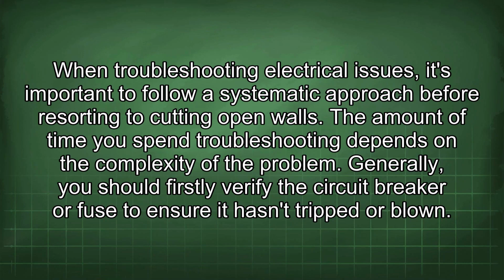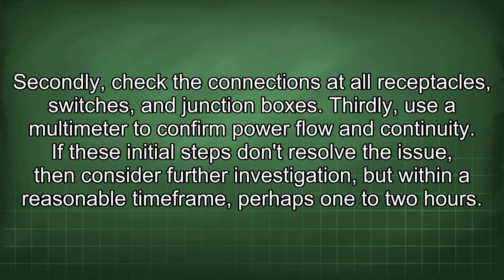When troubleshooting electrical issues, it's important to follow a systematic approach before resorting to cutting open walls. The amount of time you spend troubleshooting depends on the complexity of the problem. Generally, you should firstly verify the circuit breaker or fuse to ensure it hasn't tripped or blown. Secondly, check the connections at all receptacles, switches, and junction boxes. Thirdly, use a multimeter to confirm power flow and continuity.